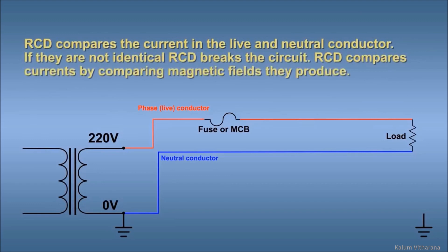An RCD compares the current in the live and neutral conductors. If they are not identical, the RCD breaks the circuit. The RCD compares currents by comparing the magnetic fields they produce.